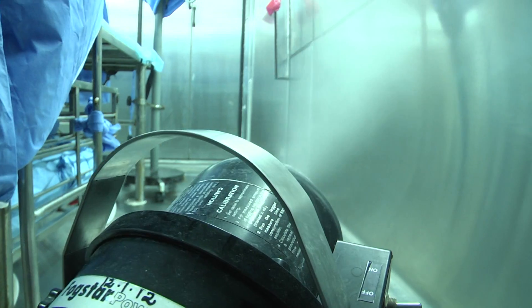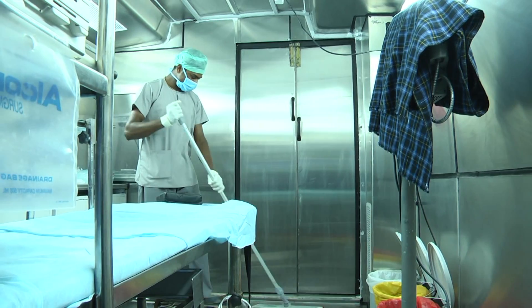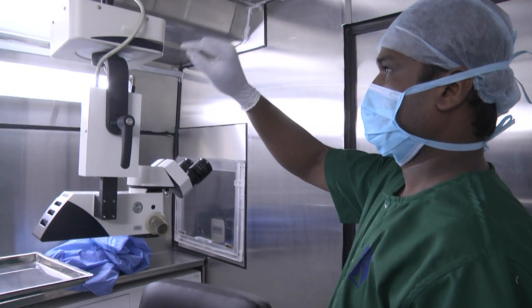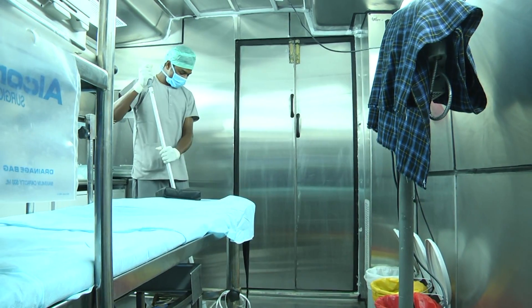The OT vehicle, also known as the surgery vehicle, is thoroughly cleaned and disinfected so that surgeries can start. The sterility of the vehicle is checked using a particle counter and a swab culture test. If and only if the sterile condition is met, the cleaning cycle stops.